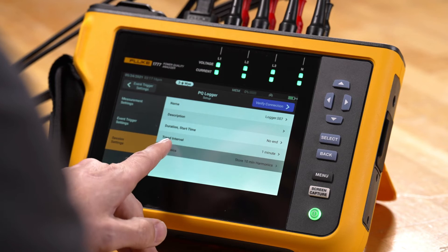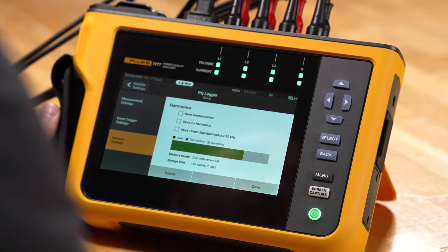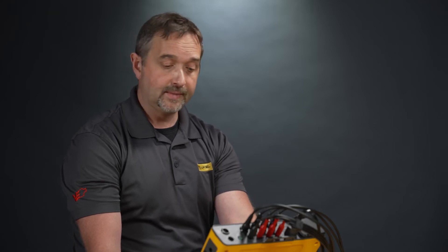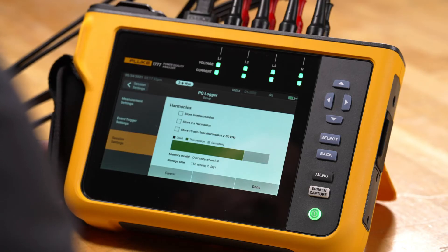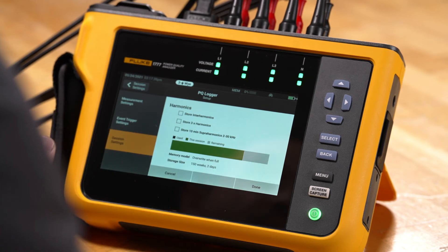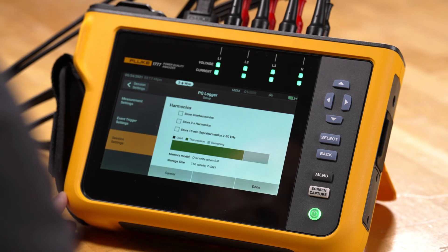We also have a harmonics option. For harmonics setup, we can store interharmonics, we can do three-second harmonic data which would be for IEEE 519 purposes, and we can also store 10-minute super harmonics which are 2 to 30 kilohertz harmonic frequencies. Once we pick these options, it'll show us how much memory consumption is taking place from those parameters, letting us know the maximum record time.